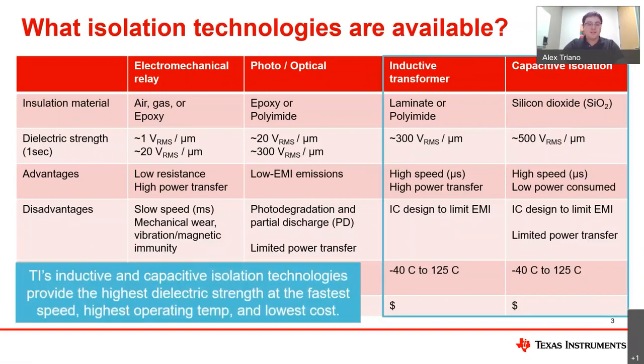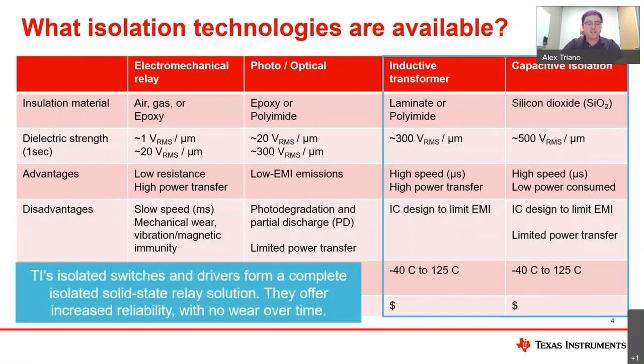In summary, TI's inductive and capacitive isolation technologies provide the highest dielectric strength at the fastest speed, highest operating temp, and lowest cost. These technologies are used in TI's isolated switches and drivers to form a complete isolated solid-state relay solution. They offer increased reliability with no wear over time since there are no moving parts.